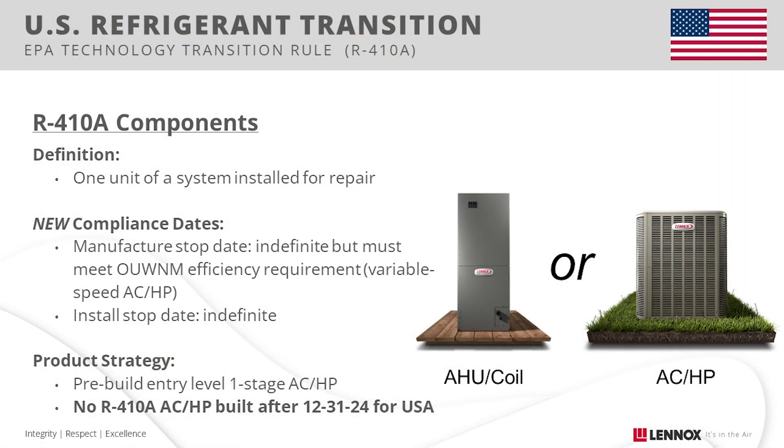Now let's talk R410A components, which refer to the individual pieces of equipment used for system repairs. The EPA definition of a component is one entire piece of equipment such as a coil, air handler, heat pump, or air conditioner. The recent change is due to an EPA requirement in the technology transition rule about R410A component pieces and what qualifies to be manufactured beyond 2024.